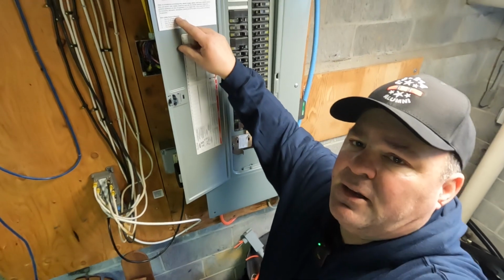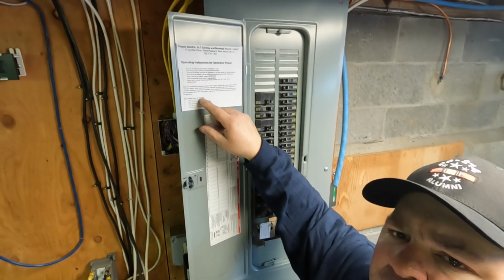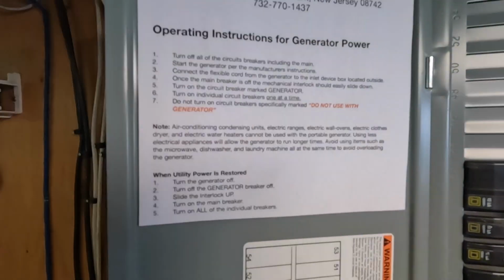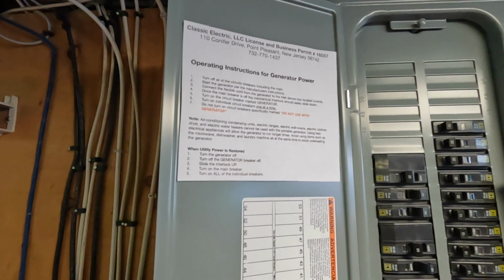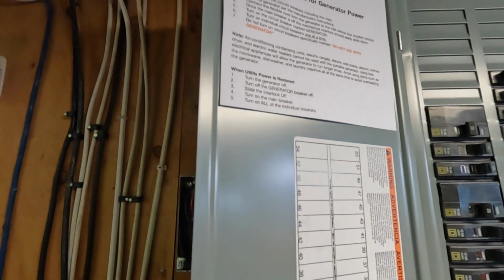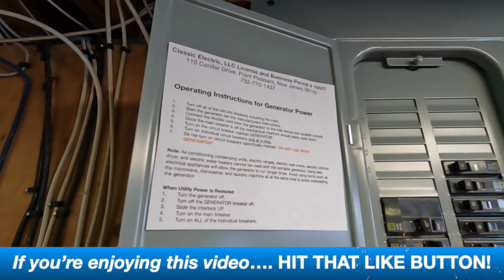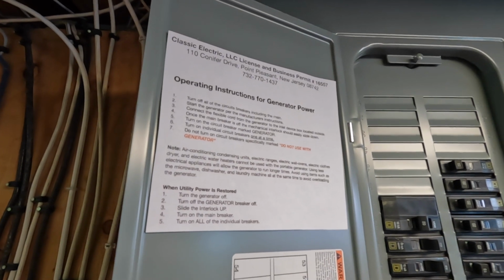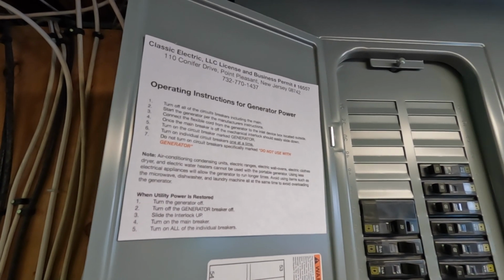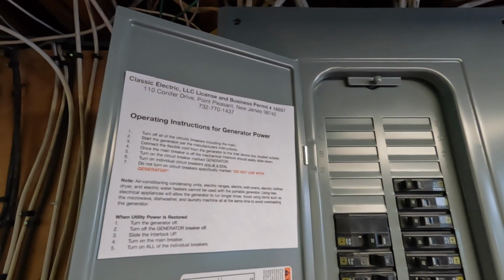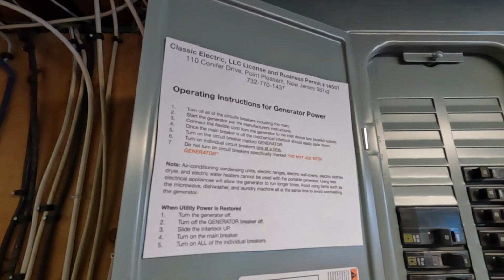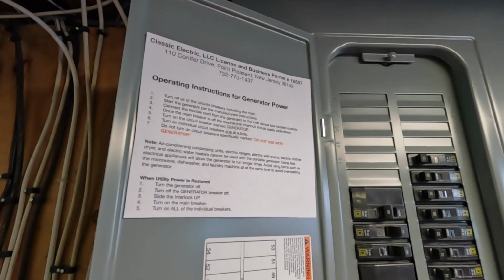Should you forget how to do this, and we don't have an outage for a year or two, I have directions right here. Here are the directions. Turn off all of the circuit breakers, including the main. Start the generator per the manufacturer's instructions. Connect the flexible cord from the generator to the inlet box, the inlet device box located outside. Once the main breaker is off, the mechanical interlock should easily slide down. It did. Turn on the circuit breaker marked generator, which we will.